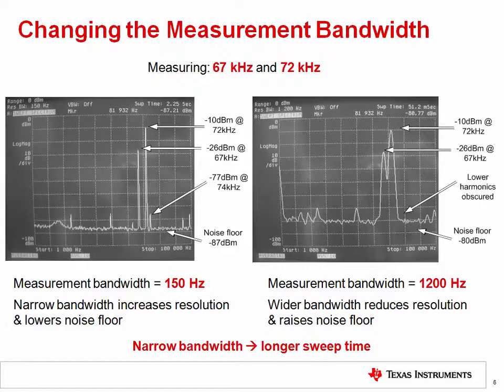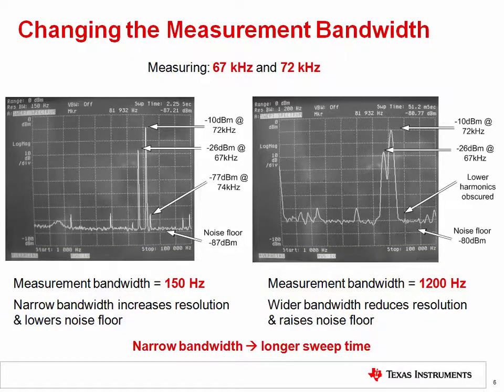The images above show a spectrum analyzer being used to measure signals at 67 kHz and 72 kHz, using different measurement bandwidth settings of 150 Hz and 1200 Hz. The narrow measurement bandwidth of 150 Hz is better at resolving the discrete signals, and also reduces the noise floor because the amount of noise captured inside the bandpass filter is smaller. The wide resolution bandwidth of 1200 Hz loses information because the wider bandpass filter captures both signals at once. So when making noise measurements, take care to use a measurement bandwidth that provides good resolution.